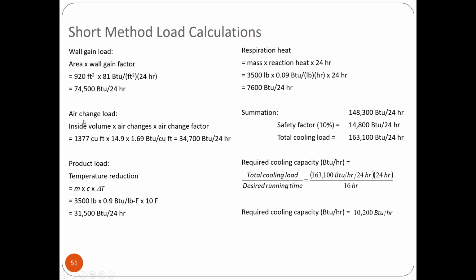Air change load is the inside volume times the air changes times the air change factor. 1377 cubic feet times 14.9 times 1.69 BTU per cubic foot is 34,700 BTU per 24 hours. Now, the product load, temperature reduction, is m c delta T: 3500 times 0.9 times 10, or 31,500. Then respiration heat is the mass times respiration heat times 24: 3500 times 0.09 times 24 is 7,600 BTU per 24 hours. So the summation is 74,500 plus 34,700 plus 31,500 plus 7,600, which is 148,300 BTU per 24 hours.